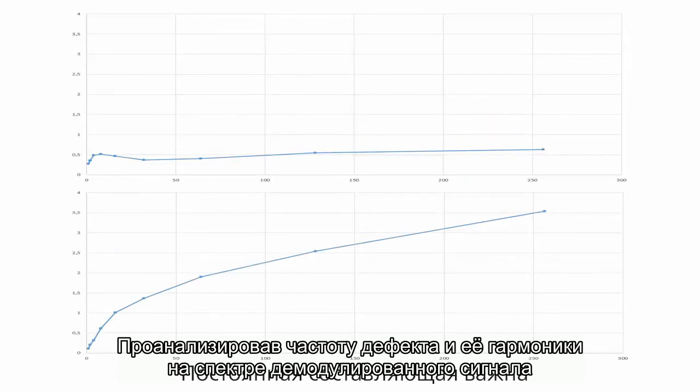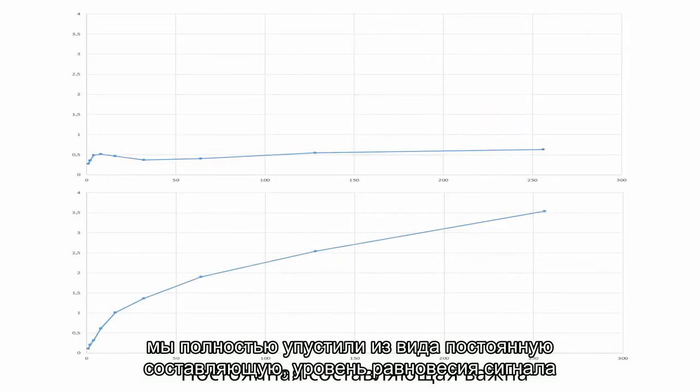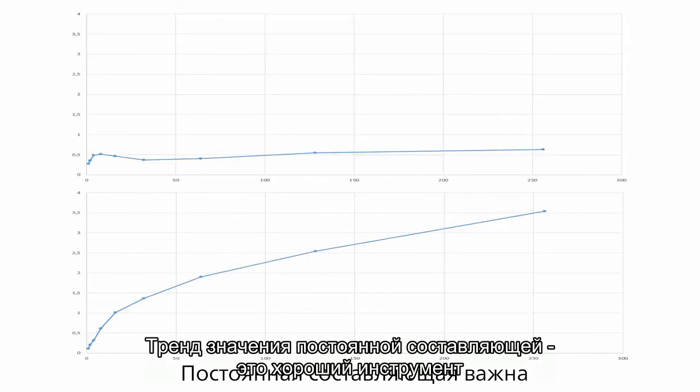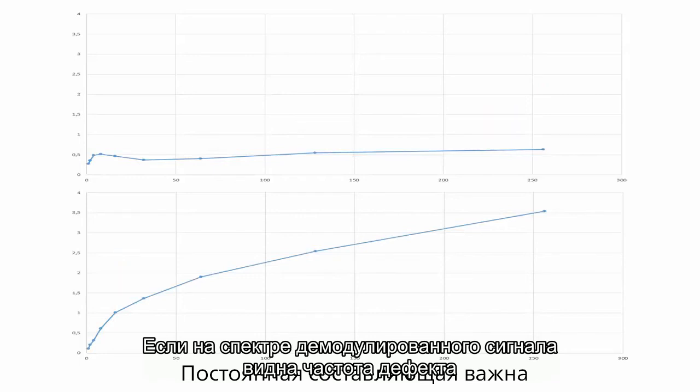When we analyzed the fault frequency and harmonics in demodulation spectra, we completely overlooked the DC value in line 0. It was a mistake. The DC trend is a good tool. If the demodulation spectrum shows the fault frequency, it is just the evidence that something happens on outer race, for example.